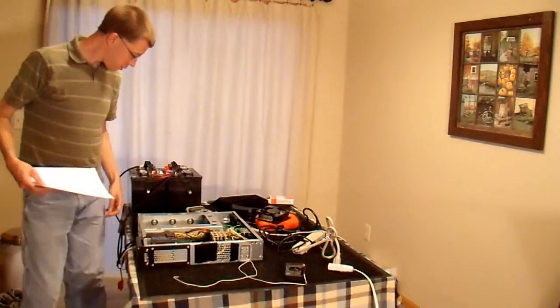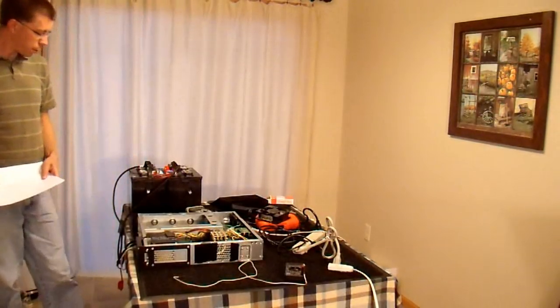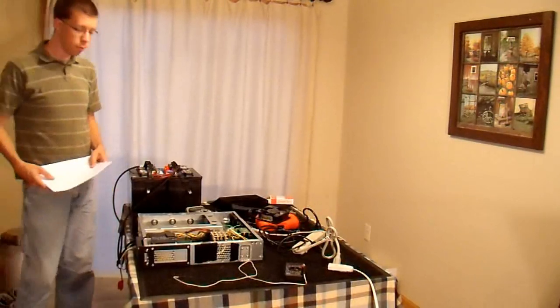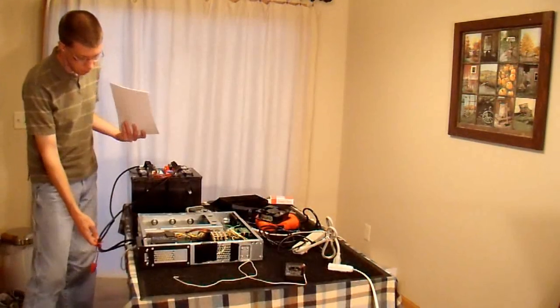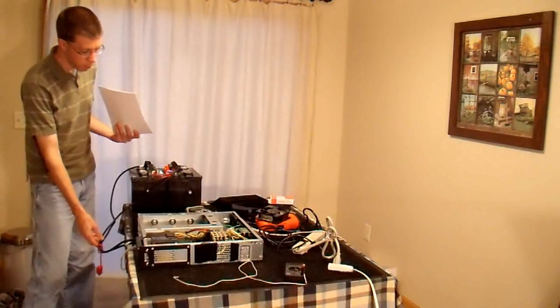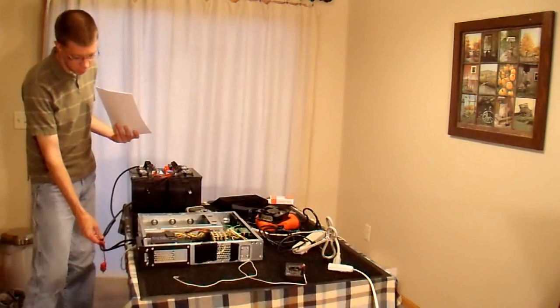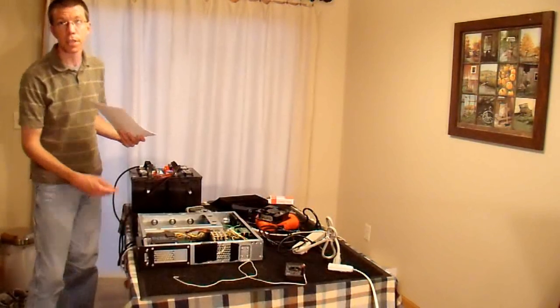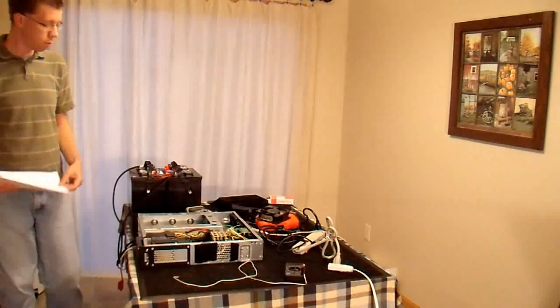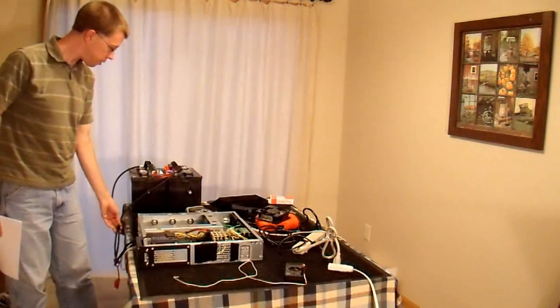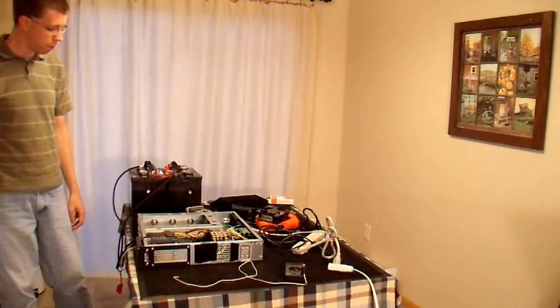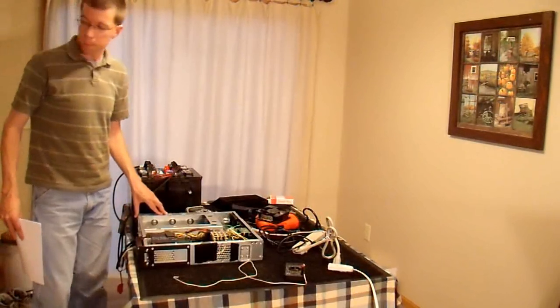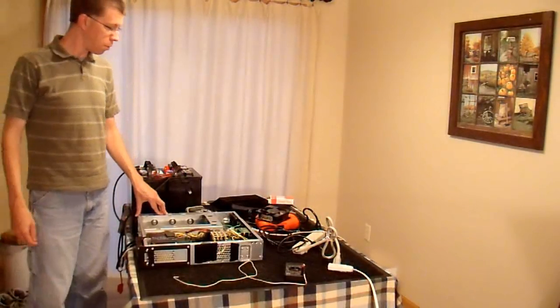But the only thing in here that I really noticed got especially hot were these cables. This test was about 80 amps continuous, and these 8-gauge cables, the jacket temperature actually got up to about 70 degrees Celsius, so they are clearly not adequate, once again. I'll have to upgrade those for the final design, but for this test, they serve their purpose.